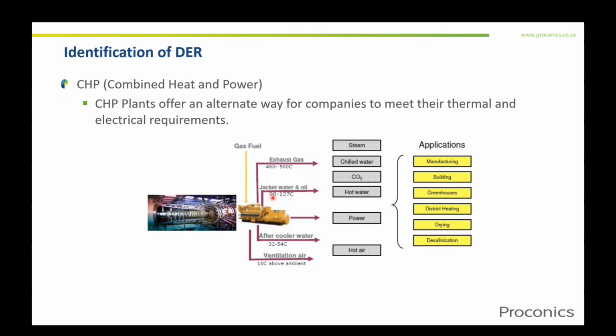You can use either a gas turbine or a reciprocating gas engine, which produces exhaust gas at high temperature, plus jacket water and oil at lower temperature, after-cooler water, and ventilation air. These can be used for heating, hot water, producing steam, chilled water through an absorption chiller, and hot air. There are various applications - it can be a replacement for an existing boiler in a plant.